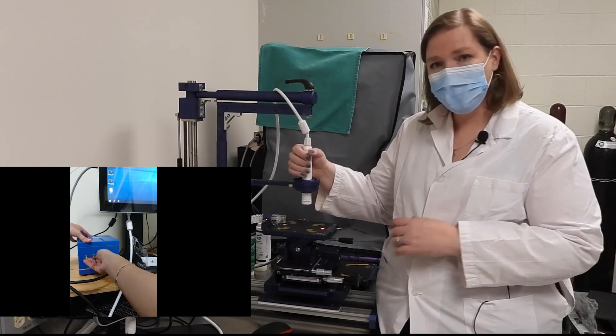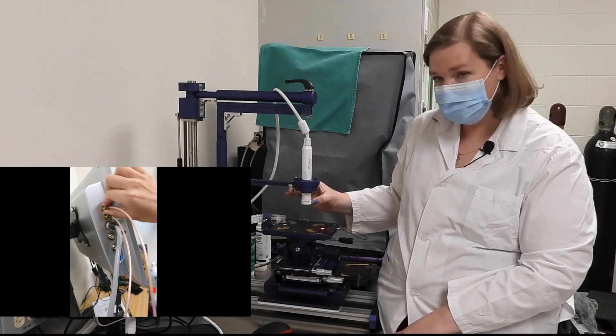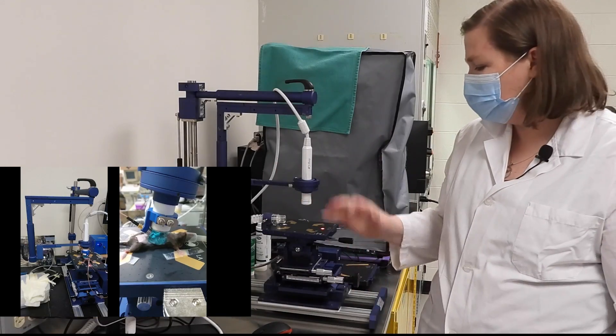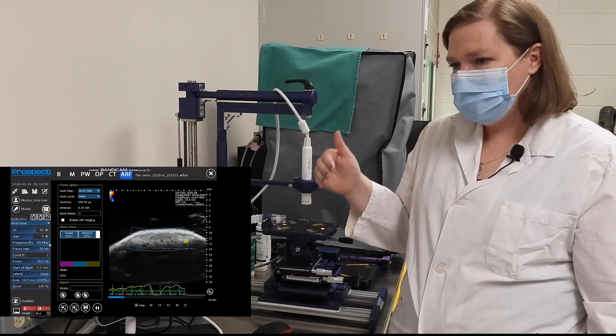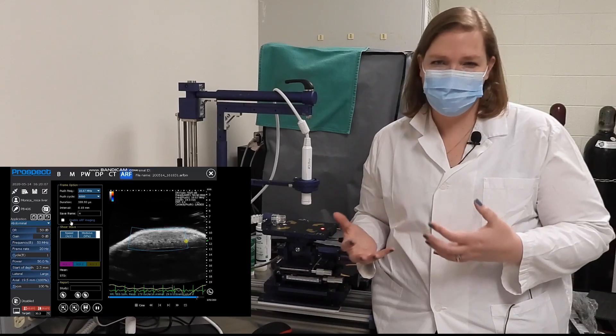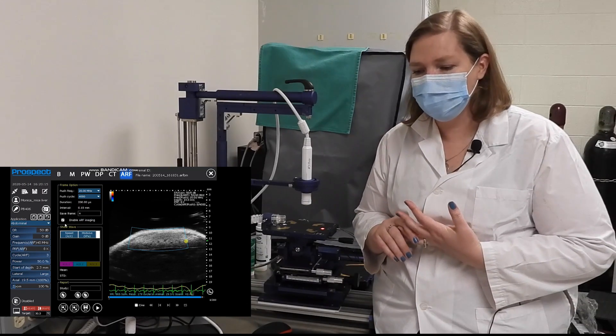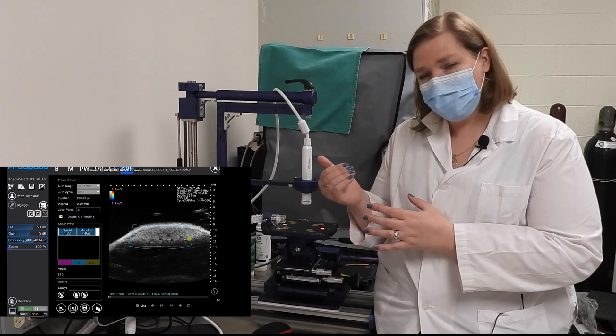The system can be used for shear wave elastography using a push probe that circles around the imaging probe, with a transmit and receive device on the side. The software calculates how fast the pushed sound wave travels through tissue and returns to the transducer. This provides an earlier measure of tissue changes — in the liver, muscle, or tendons — detecting lesion formation before it is visible, since affected tissue will show a different speed of sound.